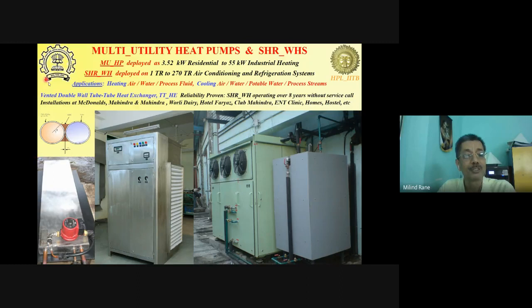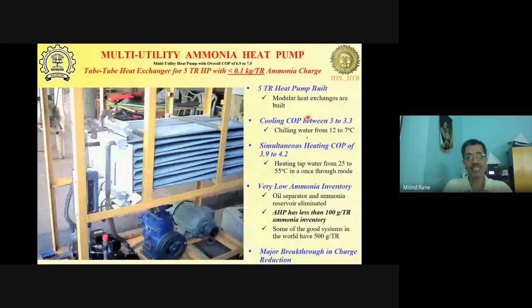So this tube heat exchanger has been core to many of our technologies that we have deployed in various systems here. The other advantage of a tube heat exchanger is that of very low inventory. Some of you might be aware that we have to switch over to more environment friendly refrigerants, with less ozone depletion, with less global warming potential, and so on. But many times the options are either flammable or toxic, and so it becomes very important to minimize the inventory of the refrigerant.